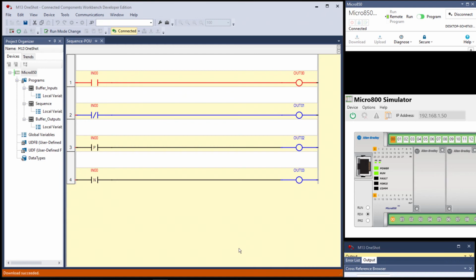Output 2 is off. Output 2 was on for one program scan. Output 3 is off. Output 3 was off. We wouldn't see output 3 go on for one scan until we turned off input 0. Putting the bit traps around these one-shotted functions, in other words, around output 2 and 3, where you set bits to see that it went on, does help. But we're trying to squeeze you through considering these just from an understanding of how the functions work.